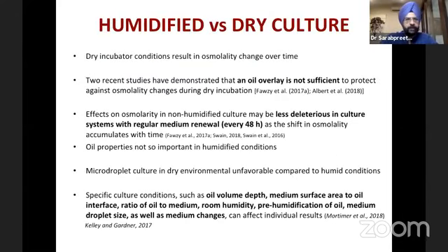If you look at humidified versus dry incubator, recent studies have shown that dry incubator conditions result in osmolality change over time. And an oil overlay is not sufficient to protect against osmolality changes during dry incubation. Effects on osmolality in non-humidified culture may be less deleterious in culture systems with regular medium renewal. Or if you are using humidified conditions, then maybe you don't even need to renew the media because there is hardly any change in osmolality. Specific culture conditions such as oil volume and depth, medium surface area to oil interface, ratio of oil to media, room humidity, pre-humidification of oil, medium droplet size, as well as medium changes can affect the results. I'll come to these points in a few slides from now.